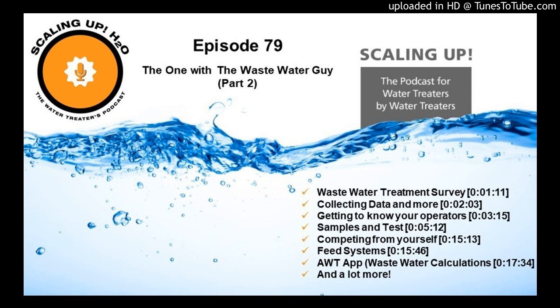The first thing you want to do is verify the current program. Does the program work in the jars like it works in the system? What are the differences? Is the floc bigger in the jars or smaller in the jars? Do they settle faster? So you really want to verify the current program and its effectiveness and understand exactly what that program is doing and what it isn't doing. Maybe it isn't meeting discharge limits, or it's not picking up all the pin floc. Whatever the case may be, you want to verify that in your jars to see what it's doing.